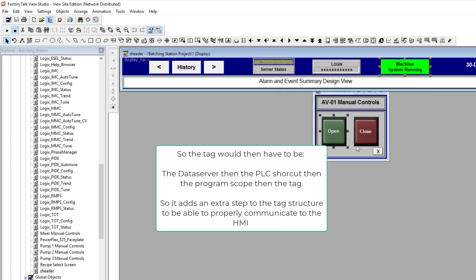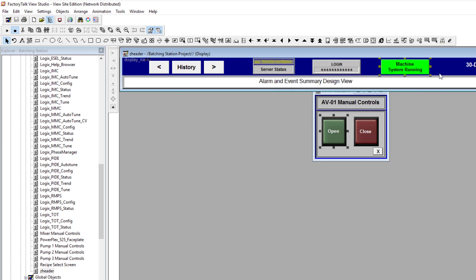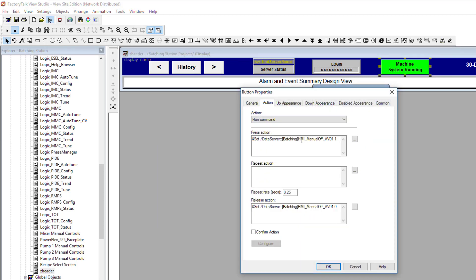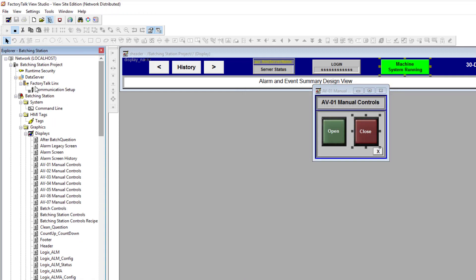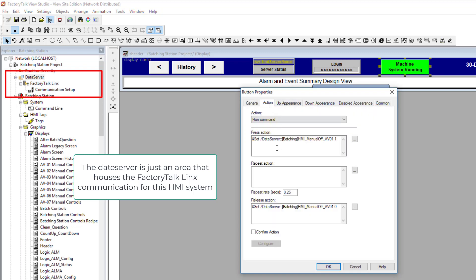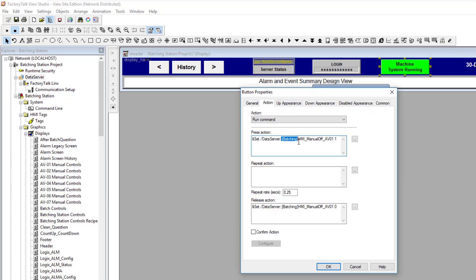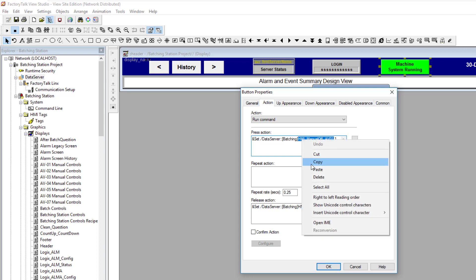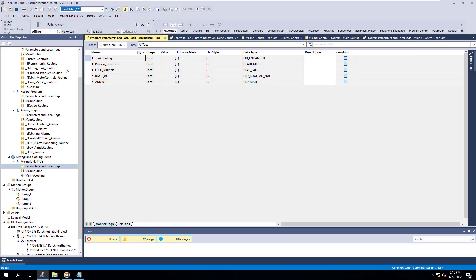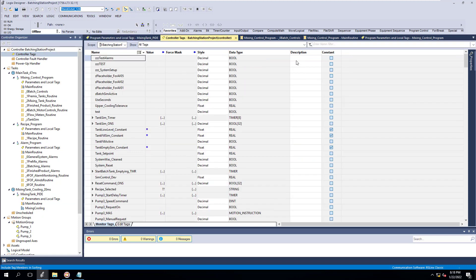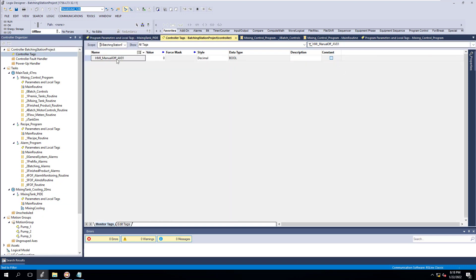The HMI connectivity is a little bit easier when it comes to direct tagging with controller scope. I'm setting the value of my data server — my data server is up here. Then I'm looking at my shortcut, which is my PLC shortcut inside of my data server, FactoryTalk Linx, and then looking at the tag directly. If I copy this over to my program, I can easily come over to my controller scope, paste it in, and find that tag right there. It's that simple.